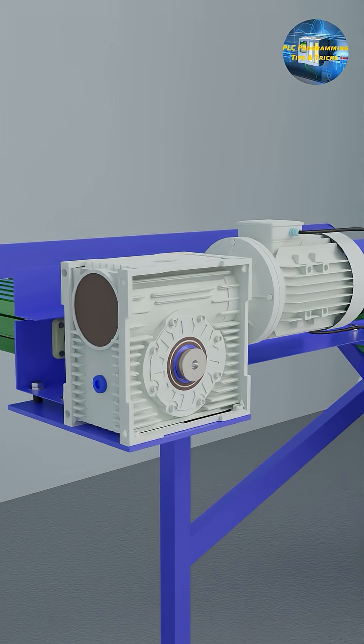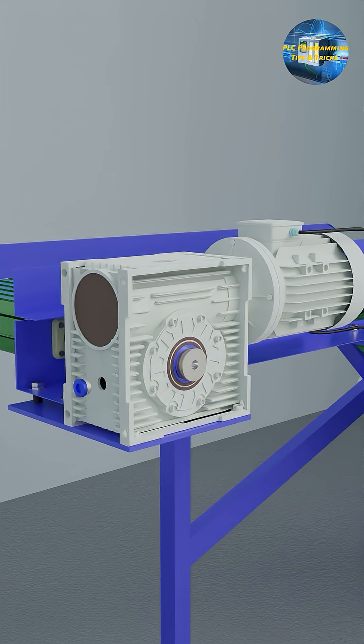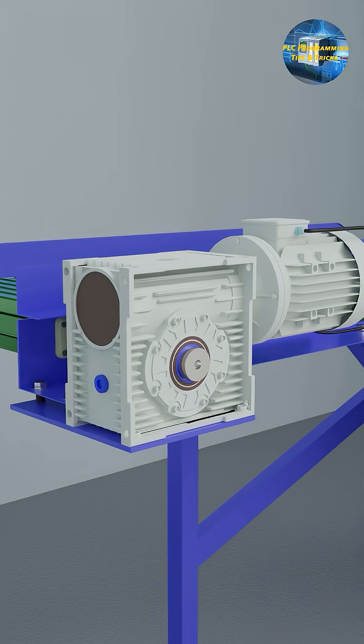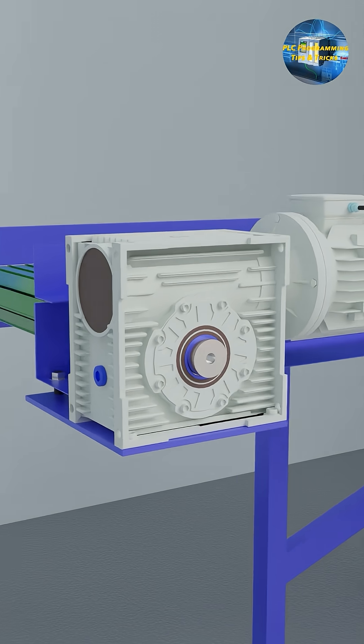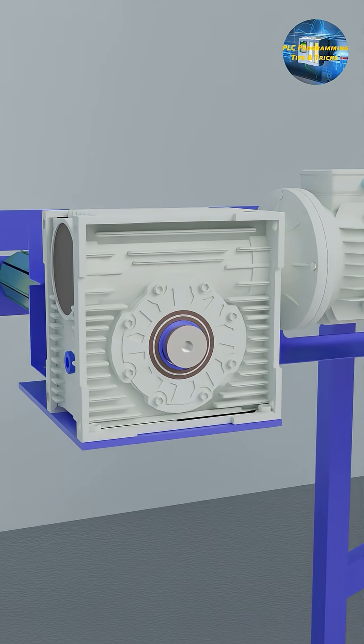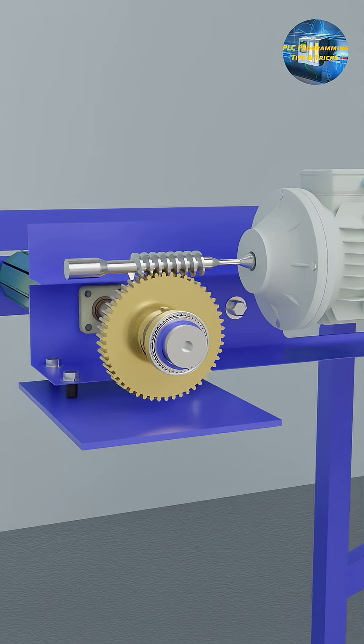we will check the gearbox and open its oil plug and check the oil level in the gearbox. Lack of lubrication oil in the gearbox will cause high friction among the gears inside the gearbox. Eventually, it can wear out the gears.